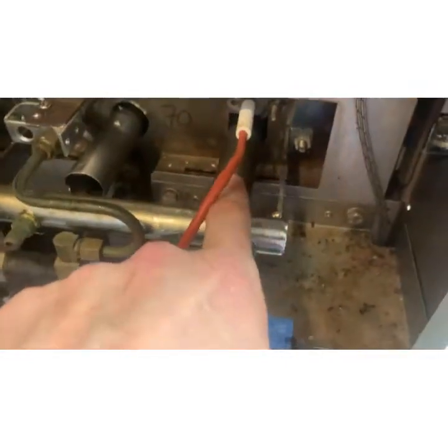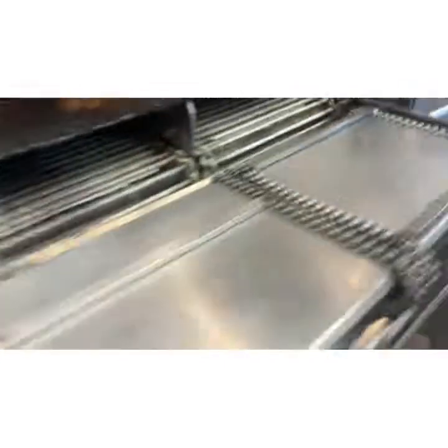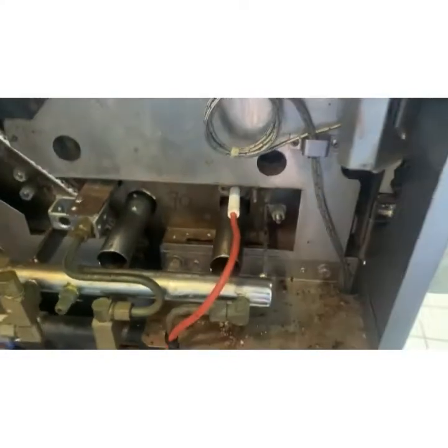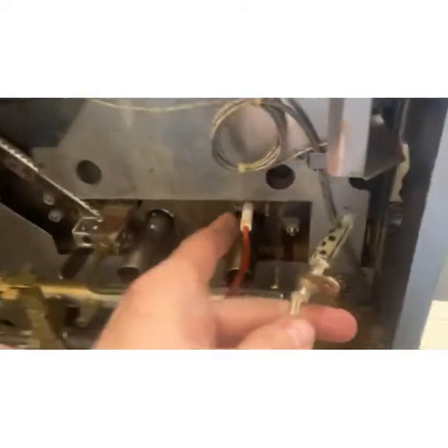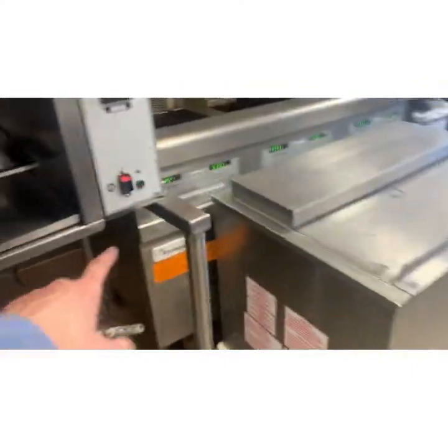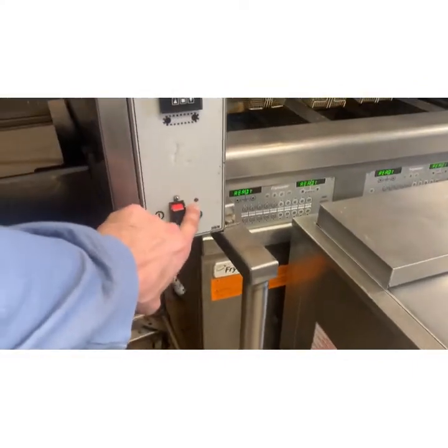When they put these tubes in, they slide in from the other side right here. And when they slide them in, if they don't get it right, it'll be poking up. They'll put the flame sensor in there, lower it down, and snap it off. Then it won't stay lit — it'll light, but it won't stay lit.